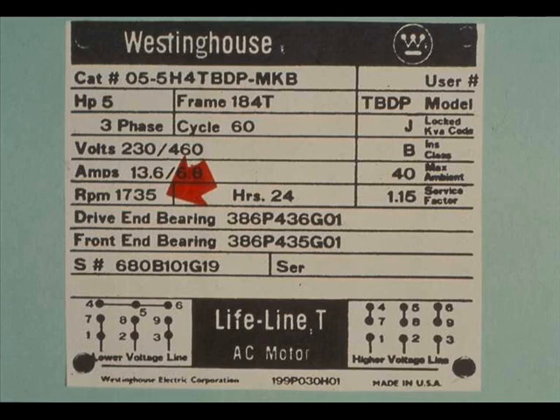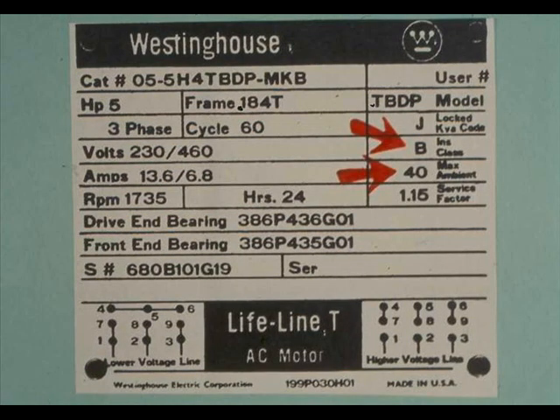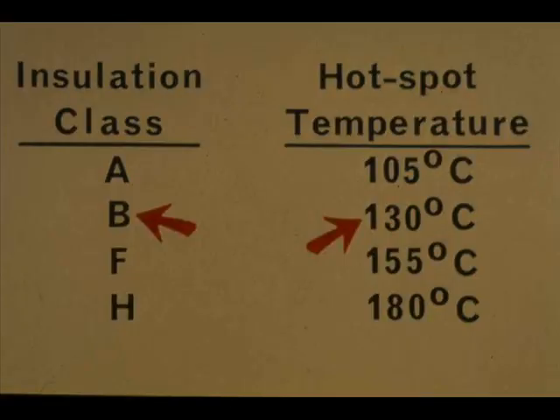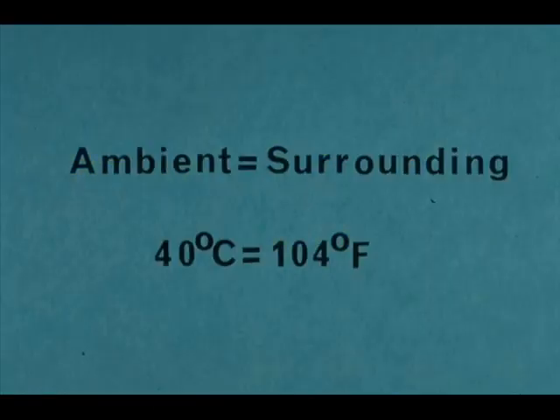The code further requires that the rated full-load speed be stated. This motor's rated speed is 1,735 revolutions per minute. The manufacturer has the option of including either the rated temperature rise or the insulation system class and the rated ambient temperature. In this case, the manufacturer has chosen the latter. The winding wires of this motor have class B insulation, good for operation at a maximum ambient temperature of 40 degrees centigrade. Class B insulation is safe for sustained operation when the hottest spot in the motor windings does not get hotter than 130 degrees centigrade, equivalent to 266 degrees Fahrenheit. Ambient means surrounding — this motor is designed for operation in a space where the temperature is not more than 40 degrees centigrade or 104 degrees Fahrenheit.